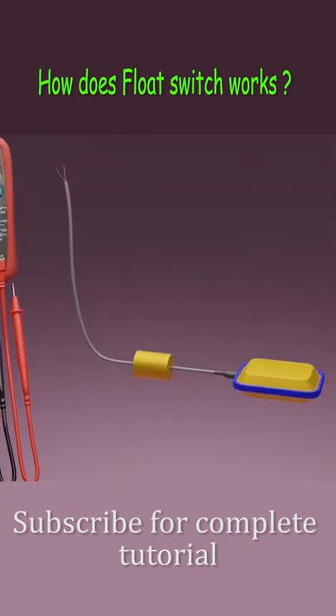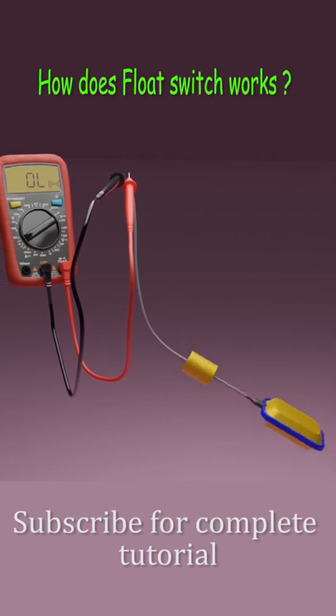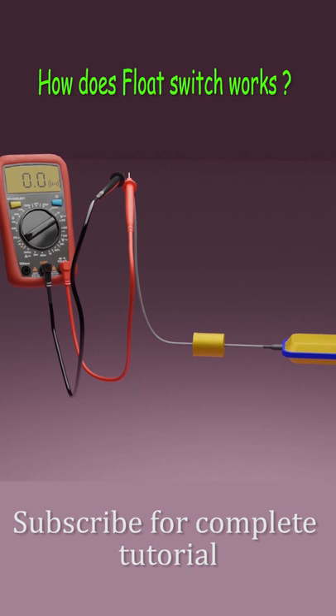If we check the continuity of the wires of the float switch with a multimeter, as the switch goes down, the multimeter shows an open circuit between these two wires. As the water level goes up, the float switch floats on the water surface and takes a horizontal position, and its wires become shorted to each other and the multimeter shows a continuity between these two wires.